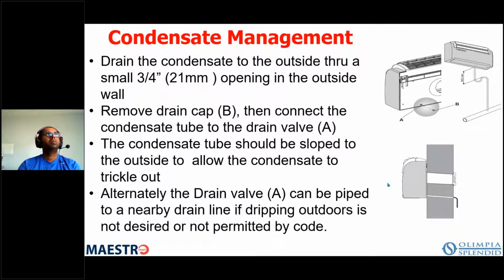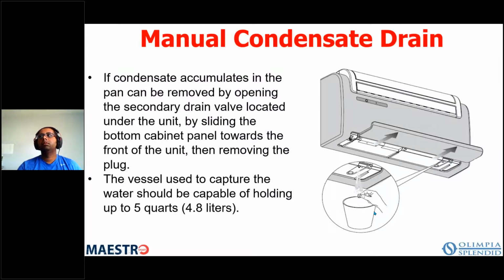Now, the point I wanted to make here before we leave the drain is you don't even have to drill a drain or have a drain. If you're in an area where you expect to have, say, very little winter operation, and of course, if your humidity levels are not South Florida high, then you don't even have to run a drain line, okay? So what you can do is keep both of those drains, the one on the bottom and the one on the top, blocked.